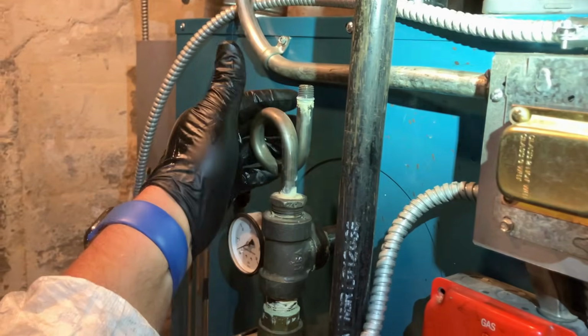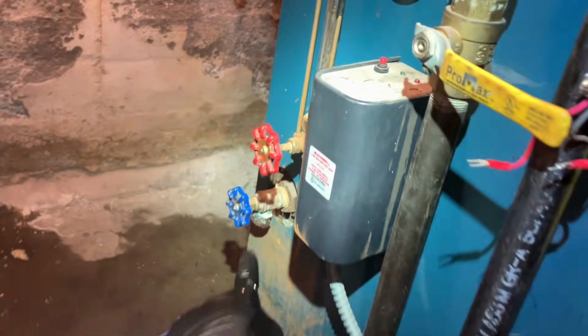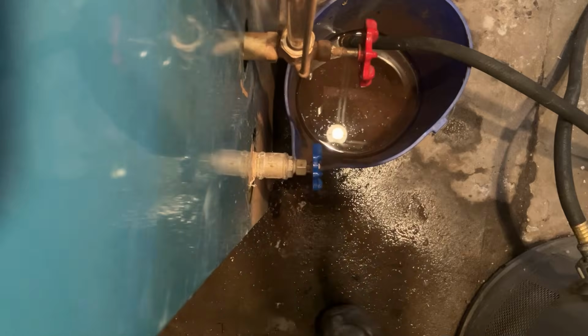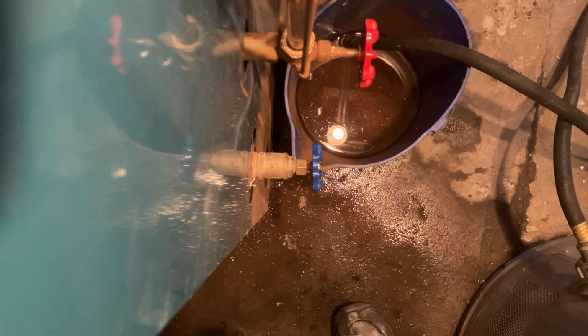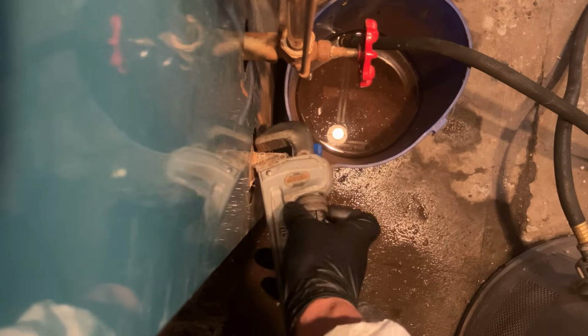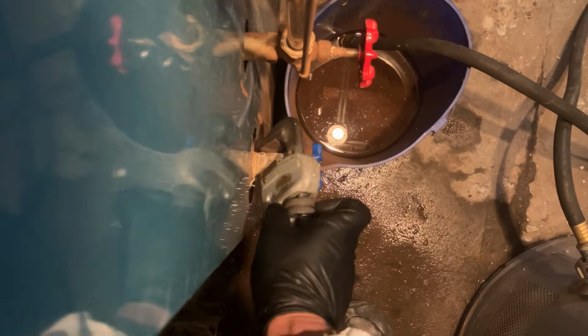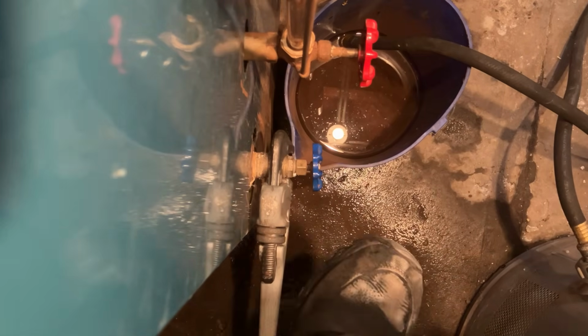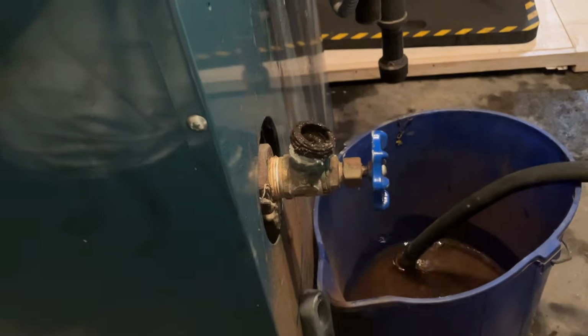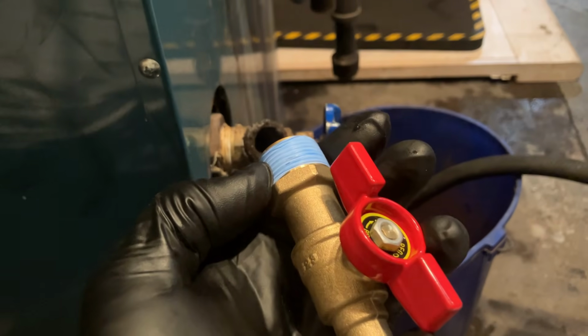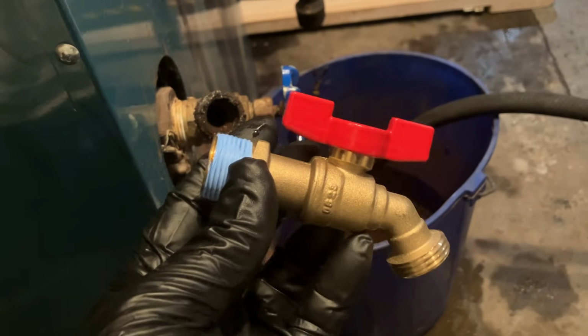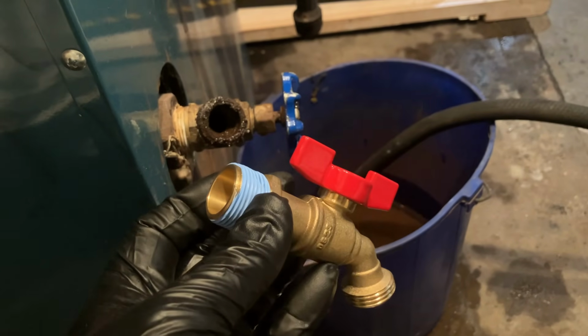All right, let's check our pigtail, make sure that's clean. Let's drain the rest of the boiler and change that 3/4 inch boiler drain that's dripping. I'm not gonna drain the boiler. I'm just gonna have a new valve ready. Okay. What, do you think I was gonna do it the hard way? Come on, use your head or your feet. Focus on what works. I got a new Webstone. No, a new Watts. 3/4 inch, full port, boiler drain. Let's get that on there.